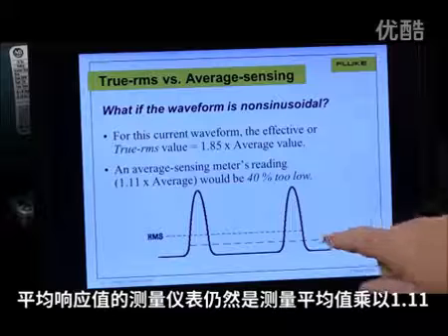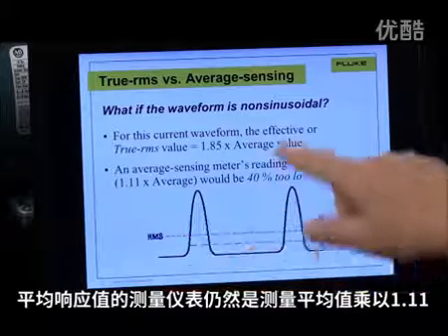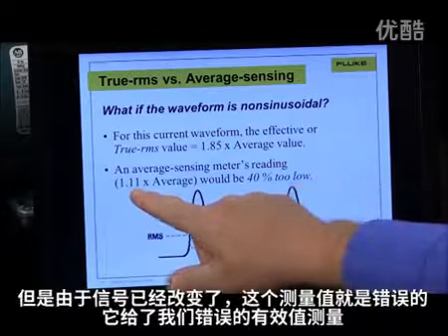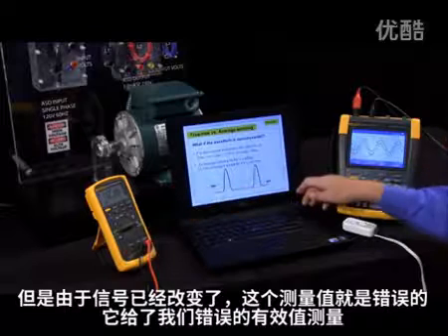the average responding meter takes the average, multiplies it by the same 1.11, but because the signal has changed, this is now the wrong number and it's giving us the wrong RMS measurement.